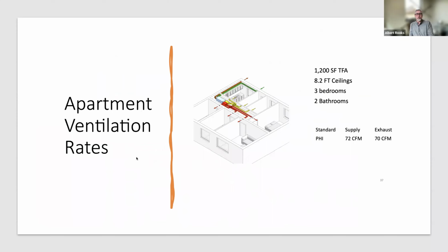So the ventilation rates, when we say, okay, we've got a building, we're going to start retrofitting ventilation and HRVs into it, we start with kind of understanding the standards and the designs. Passive House would look at this 1,200 square foot apartment with 8.2 foot ceilings. It's an imaginary space. It's got 3 bedrooms, 2 baths. And so Passive House would look at it and say, we need 72 CFM for supply. And the supply is based on how many people are in it. And exhaust, it would need 70. And those two numbers are different.